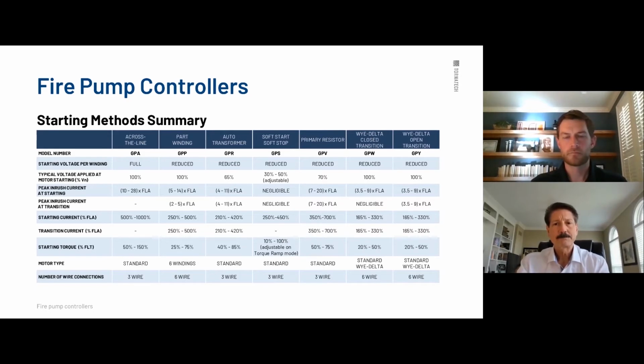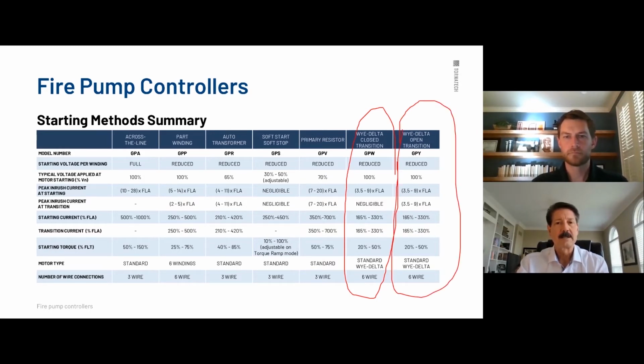The last 2, Y delta closed, we get a lot of demand for that still. And Y delta open. I'll show you briefly what those mean on future slides here. But again, you notice there's six wires. And on new applications, I always say, hey, for a 3-wire application, use an across the line or a soft start reduced voltage rather than a Y delta open or closed, because it takes 6 wires. It's twice as much labor, twice as much material to connect it.